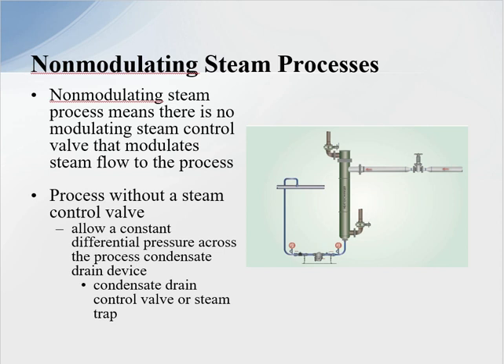Non-modulating steam processes exist in our steam systems today. With this type of system there is no modulating valve, so the process modulates differently. When there's no modulating valve, there is a constant differential pressure across the drain devices. Therefore, we can take elevation advantage and also go into a pressurized return system.